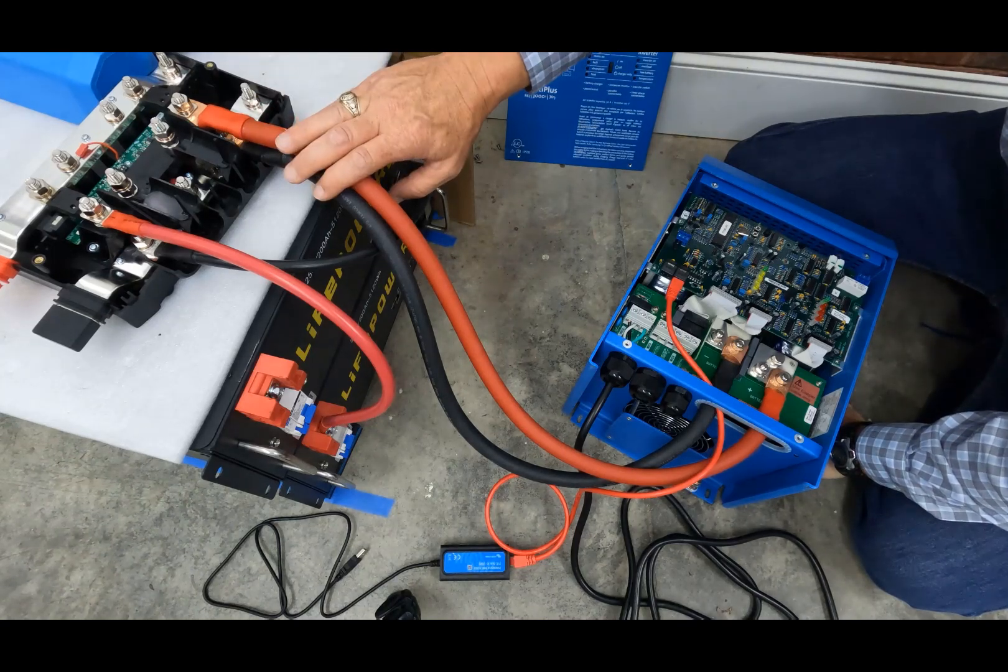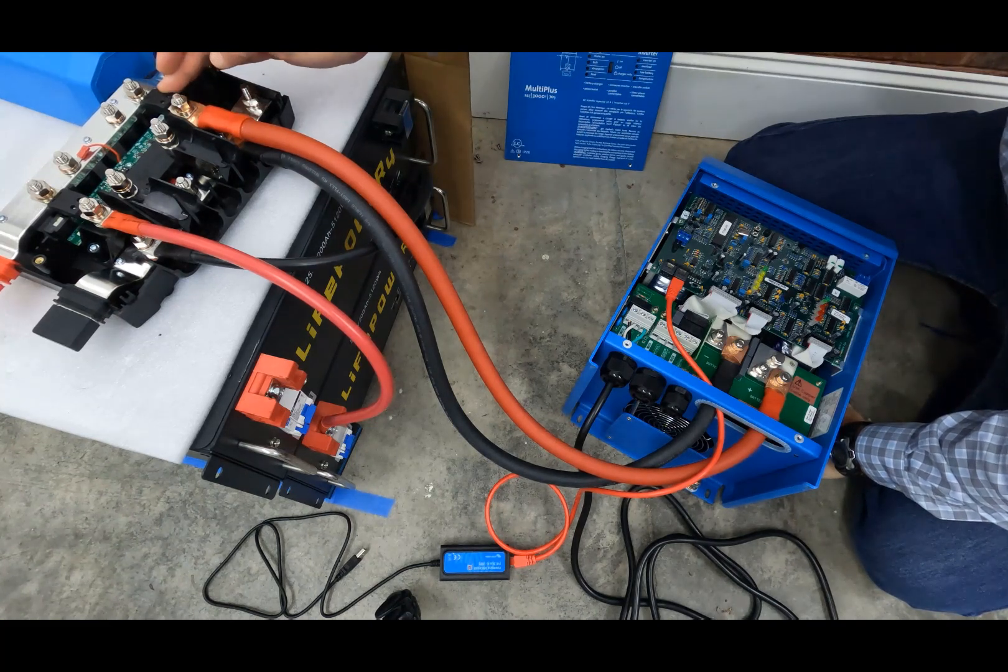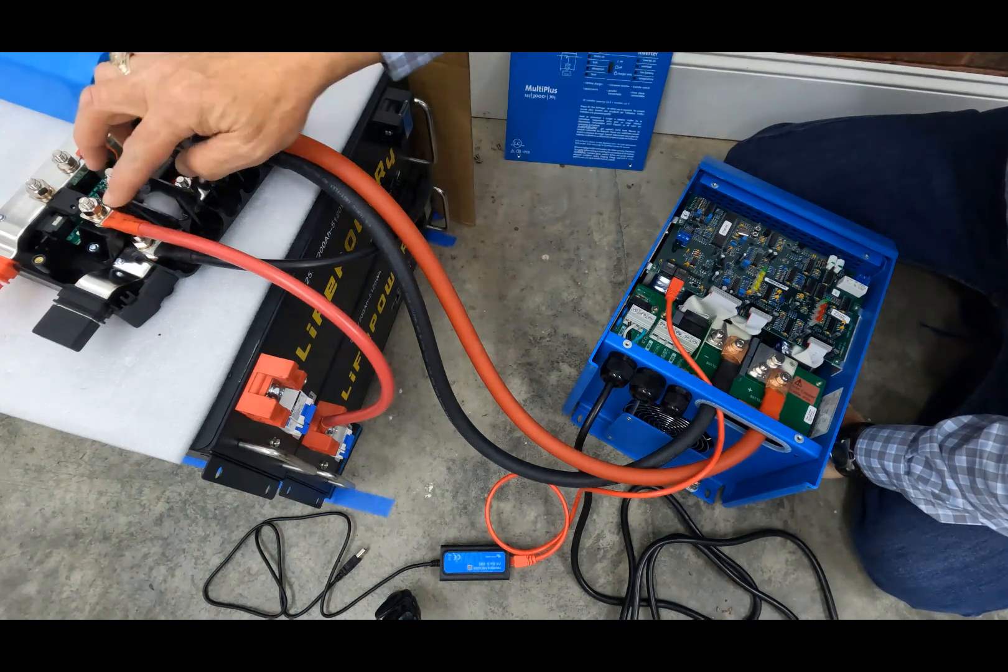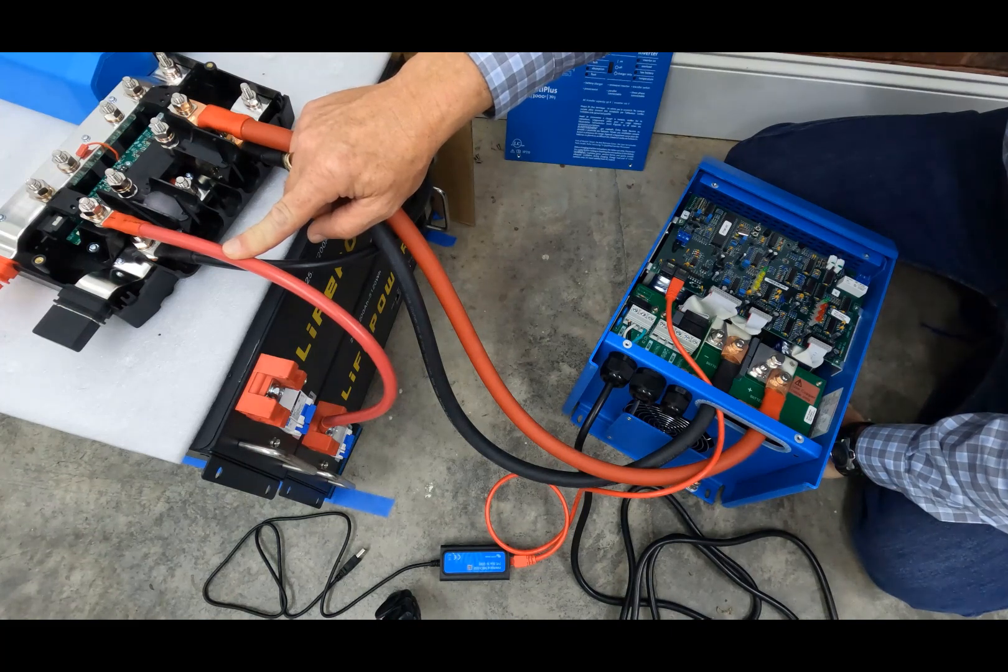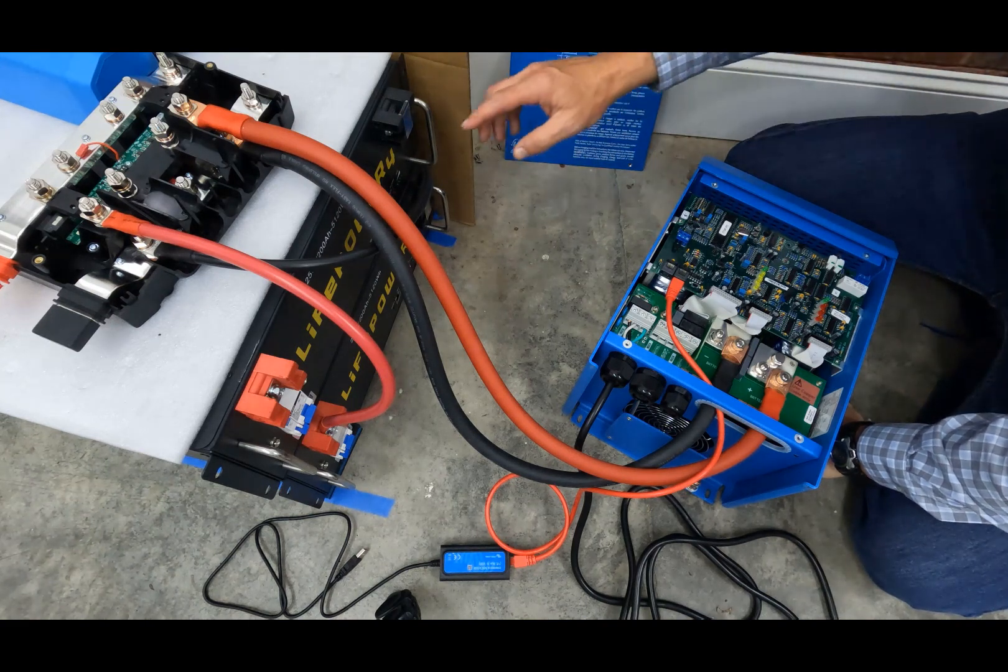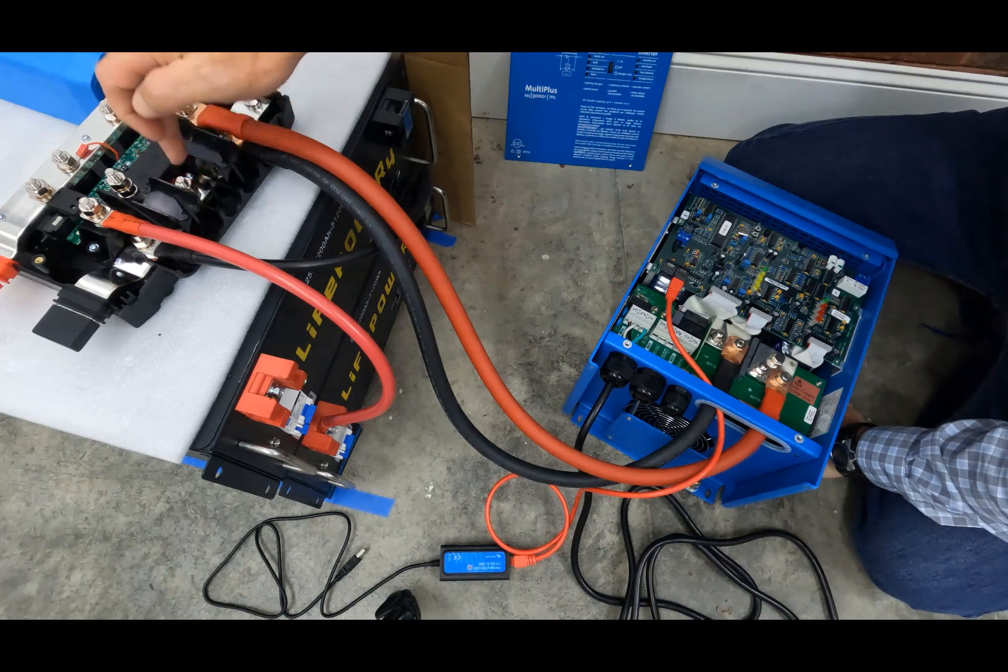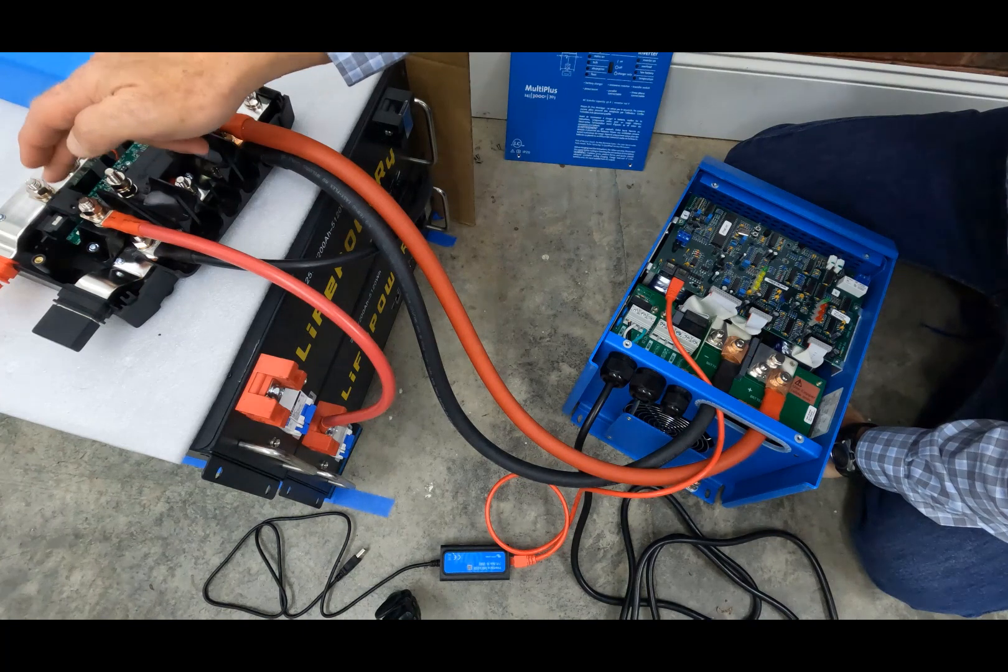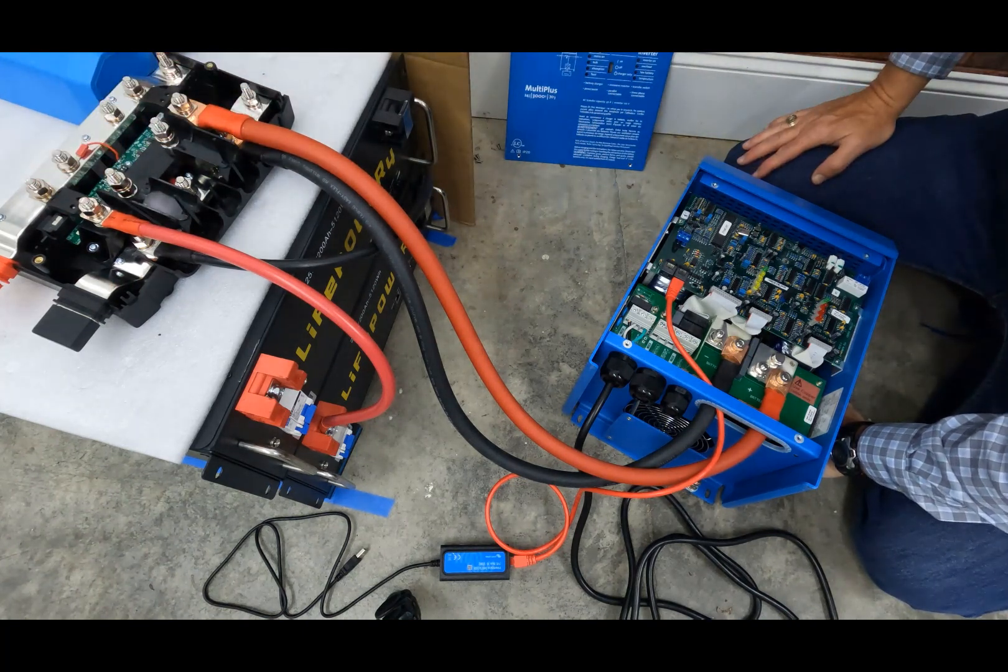So bringing in the cables from the Victron, I have a 400 amp fuse. It's larger than I need, but we're just doing basic charging of the battery. Then I've connected in the battery from each of the terminals using two-gauge wire, and I've put a 100 amp fuse on this side as well. So just an easy connection coming back in, and the negatives are connected on this bus bar already, but the positives are going through the fuses in case there are any issues to make sure that we can connect in and get that connection between those.